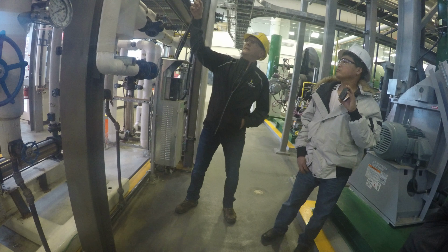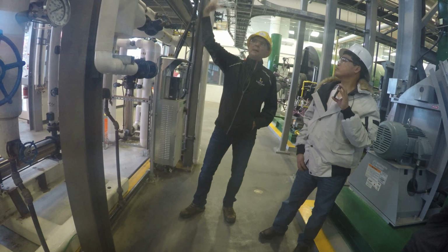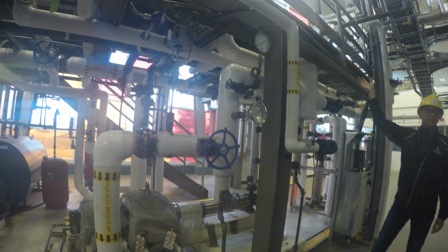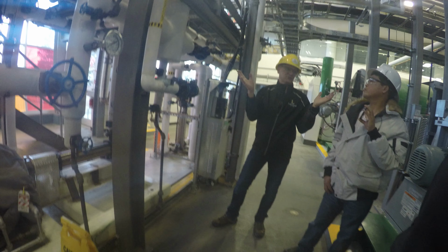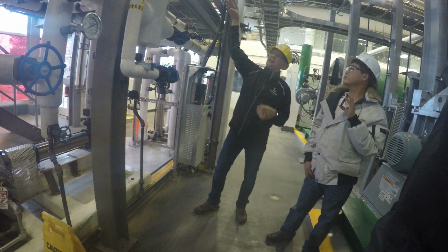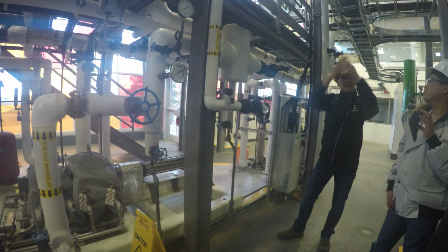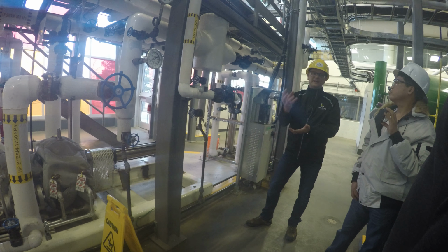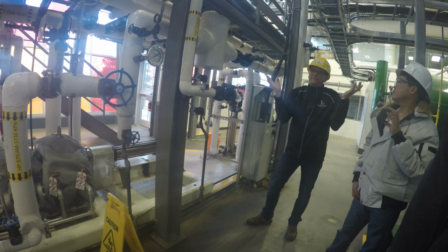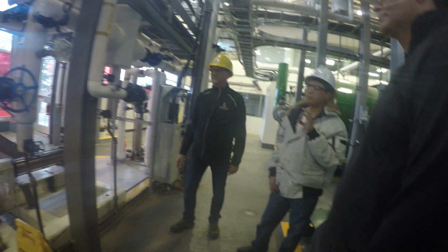There's a reason why deaerators are always up on a raised platform, because you've got water sitting there at 112 degrees C, and as soon as you try and draw it with a pump, you reduce that pressure and it flashes off to steam, right? So you put your deaerators on a platform, and we wish this thing was up about another 2 feet, because it puts head pressure on your pump, so that you're actually moving liquid at 112 degrees C. As soon as you drop that pressure, it flashes to steam, and your pump cavitates.